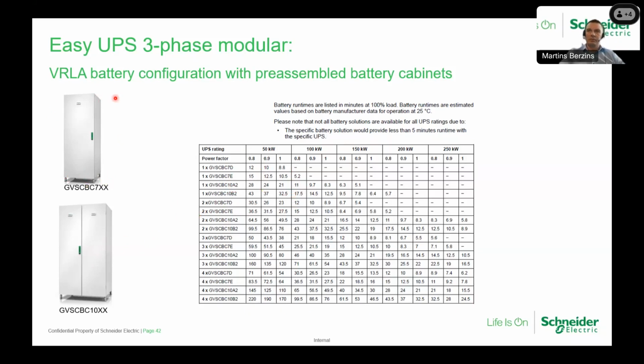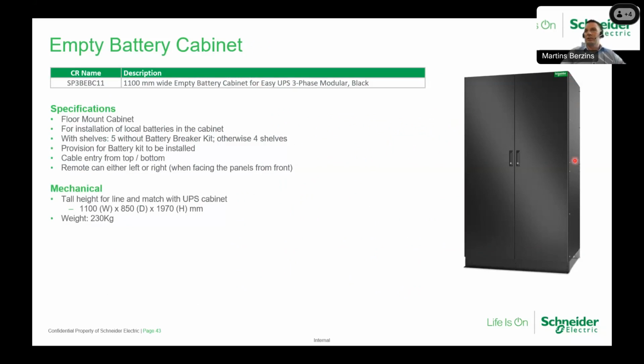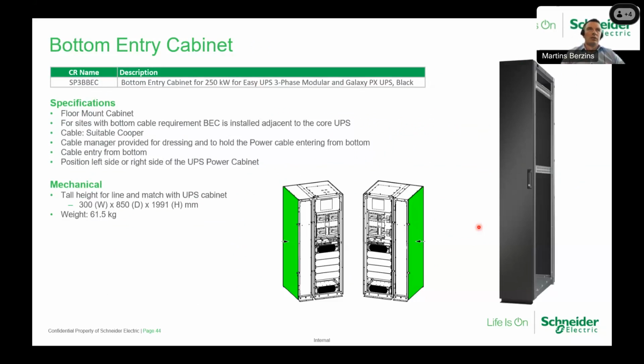So if this difference in color is not suitable for you, and you want everything in the same color, then we have this empty battery cabinet, which is black. But in this scenario, there are no batteries installed inside, so batteries will be delivered separately, and you have to install the batteries on the shelves inside this particular cabinet. Regarding the bottom entry, the UPS has top entry cables, but we have this additional cabinet, 300 millimeters wide, which you can install on the left or on the right side of the UPS, and have this bottom entry option. So there are no bus bars connecting to the sides of the UPS. It's basically just a cabinet, 300 millimeters, where you can pull the cables up to the top of the UPS and then connect from there.